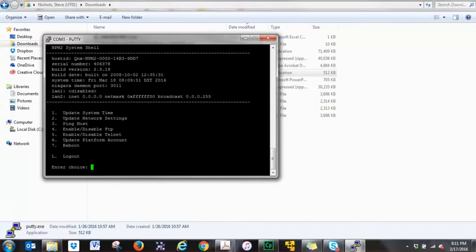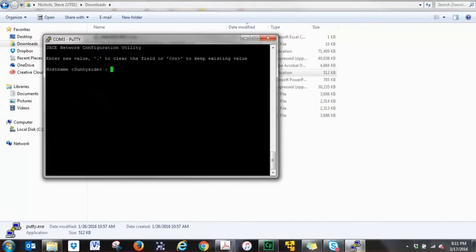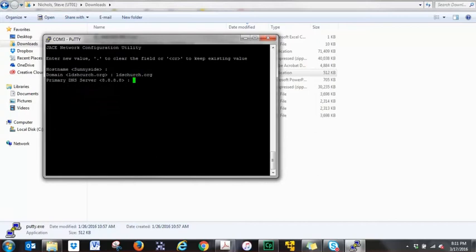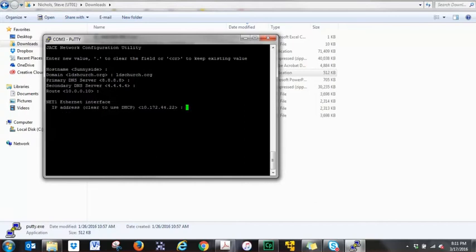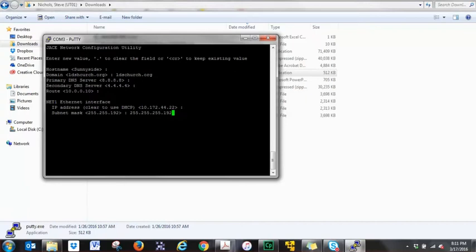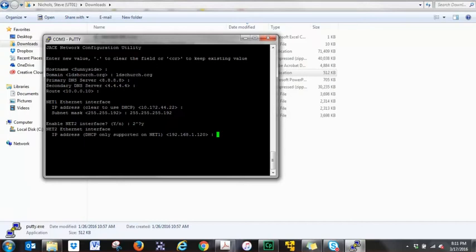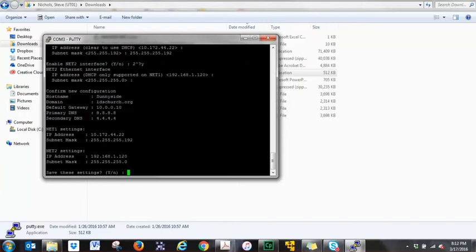Now we want to make sure that everything was entered correctly, because it looks like I typed some things wrong. So let's go back into 2 again. Sunnyside is correct. But that is incorrect. So type in ldschurch.org. And we'll just say that that's the DNS for now. Secondary DNS. The router information you get from global support or your IT group. Your IP address that you want to use on your Webstat or your controller. Your subnet. 255.255.255.192. And if you wanted to check port 2 again, hit yes. 192.168.1.120 is correct. And the subnet is correct. And we want to save the settings. Yes. Enter to continue.